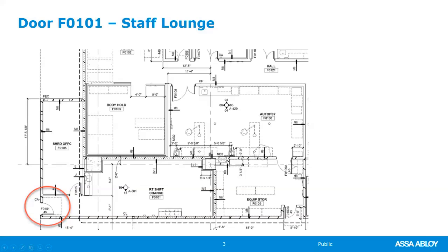Do I need to get back into this space if there is a fire? If there is a fire, I'm going to go down the hall and around the corner to the stair and get out of the building using the stair. There's no need for me to go back into this room during the fire at all, ever. Once the fire is either out or it was a false alarm or whatever, authorized people can get back into this space. This can be fail secure.